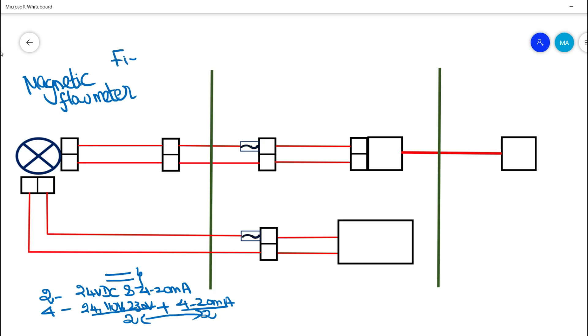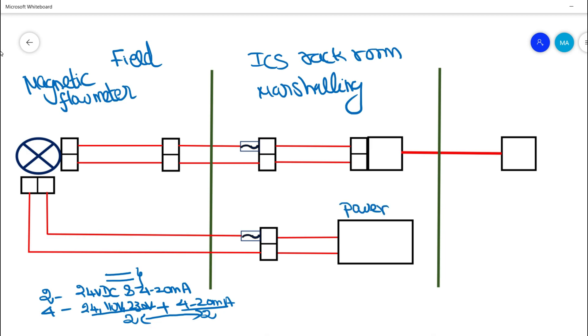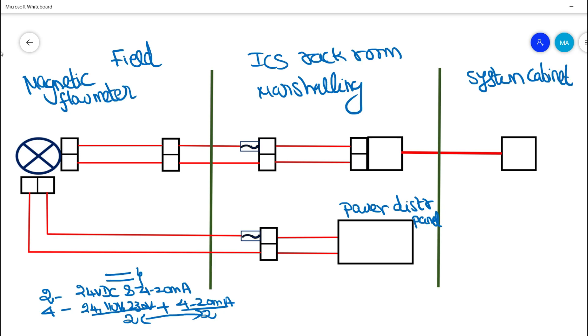Normally we have three different sections in the loop diagram. There is the field section, and then the ICS rack room. In the ICS rack room we have a marshalling section. Additionally, we have a power distribution panel — this is the only additional component in a 4-wire loop diagram compared to a 2-wire system. And then we have a DCS system cabinet. These are the basic sections and components used in a 4-wire loop diagram.